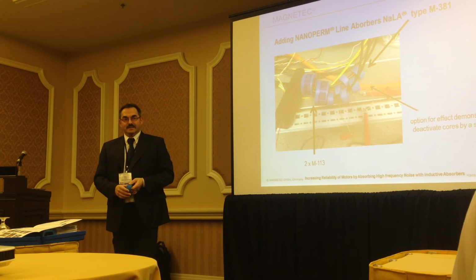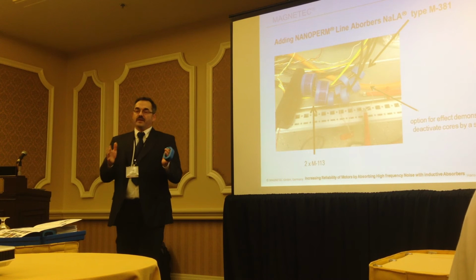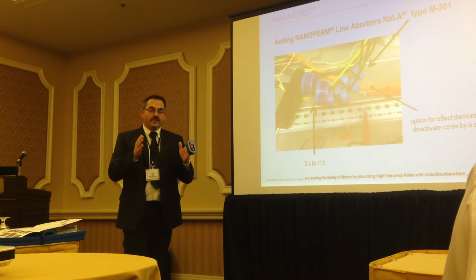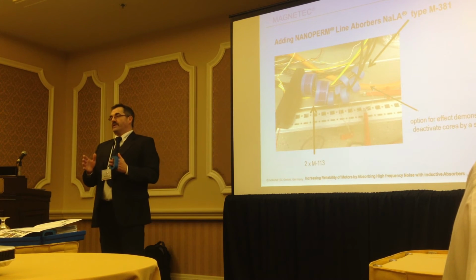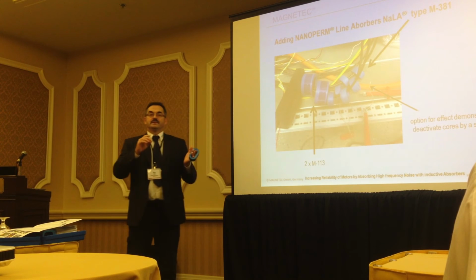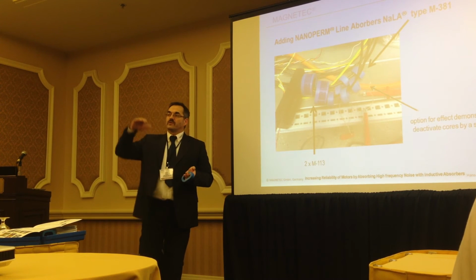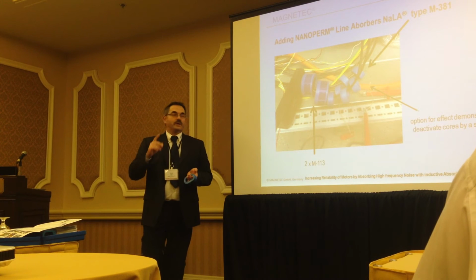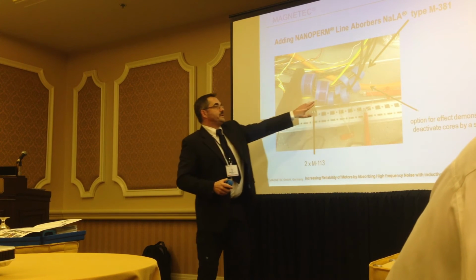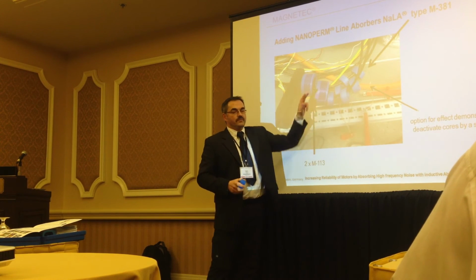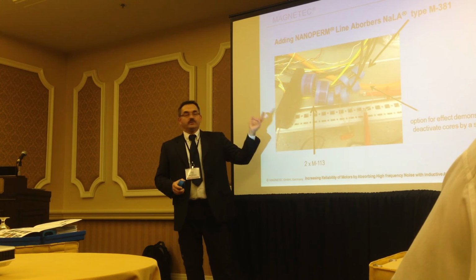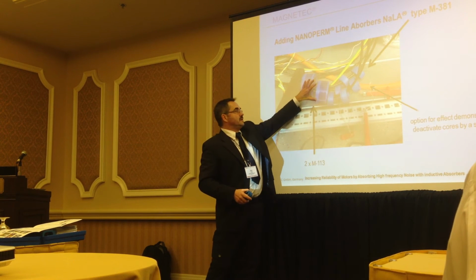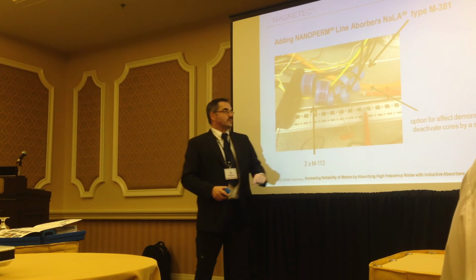The common mode is nothing else than the difference between the three phases. So if you already reduce the harmonics on the differential mode, the common mode is dropping down too. So you need both, you cannot do it alone with differential mode cores, meaning NaLAs. You need the right combination between the common mode cores and the differential mode cores.